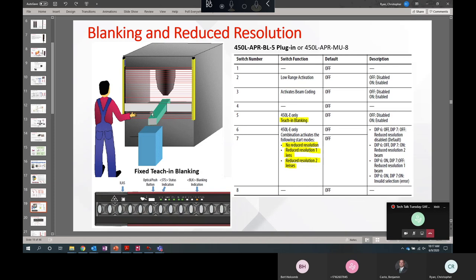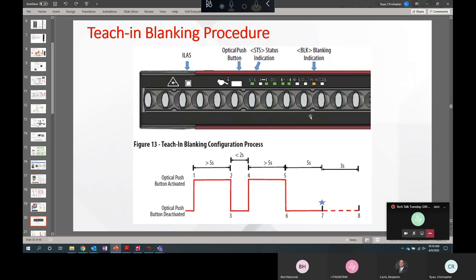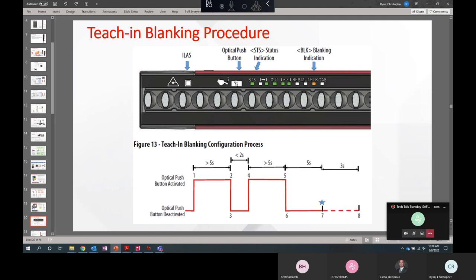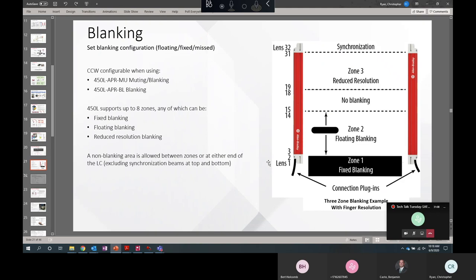It can be taught. So the blanked area of the light curtain right between here, this is always monitored, which means that if this part is moved away and the receiver sees these beams, you're going to have a fault. With teach-in blanking, as I said, beams are taught. With the new firmware update, you can actually program the blanked area in connected components workbench following the procedure. And this is the procedure. And this procedure is required anytime you configure a new configuration in your light curtain. I'm not going to show this because I have my light curtain set to software configuration. However, this is how everybody's been doing it. If you're familiar with the light curtains in the past, what I usually do in this situation is get out a stopwatch. You have to get really accurate here, just over five seconds, or at least for just under two seconds. And put your finger back on this mark right here, this white square with the picture of the hand. And that'll confirm that your new configuration is active.